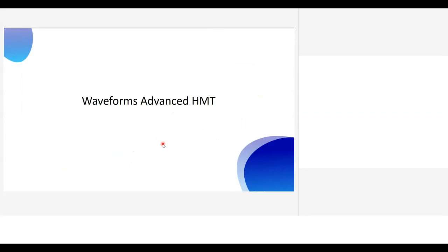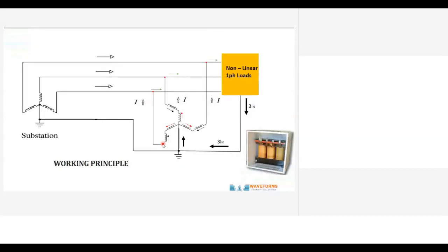It is very useful in computer centers, where you have single phase loads. This type of filter can reduce harmonics. Even if they have a UPS, the UPS having a high impedance, the voltage waveform can get distorted, and the ride through facility can reduce substantially. So you can introduce it between the UPS and the load. You can use this filter in the double winding type of zigzag transformer or autotransformer.